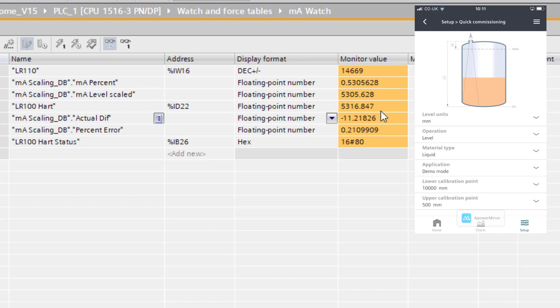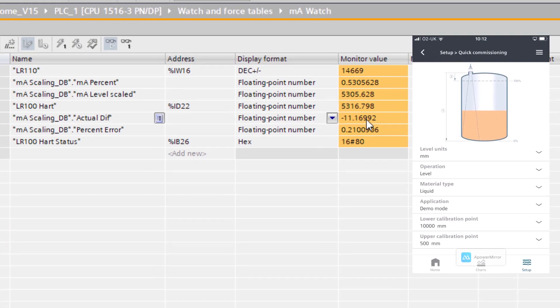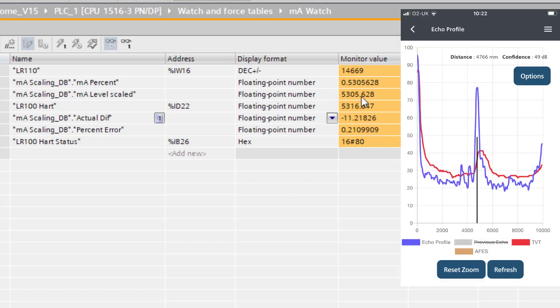I'm going to put this back to zero so my two units are the same, and then we're going to start looking at the error. What I have here is my millimetres difference, my HART value, and my milliamp value. The level itself is dead steady, which you can see from the HART value.